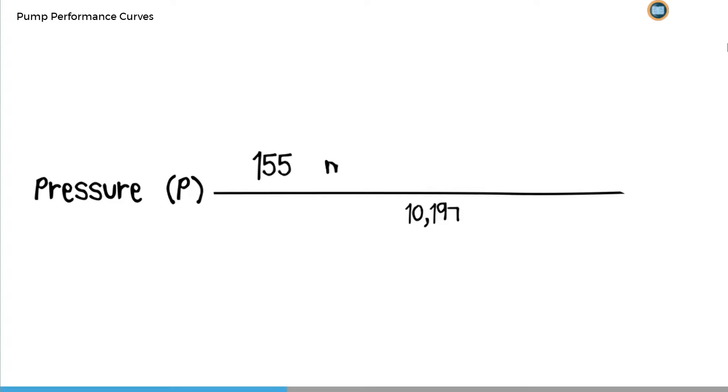For example, a head of 155 meters and a density of 890 kilograms per meter cubed would be equivalent to a pressure of 13.5 bars.